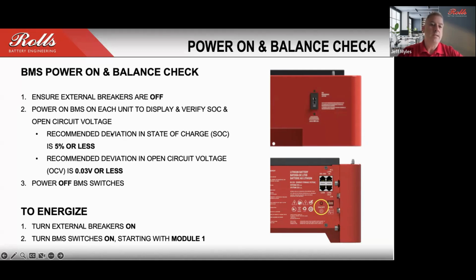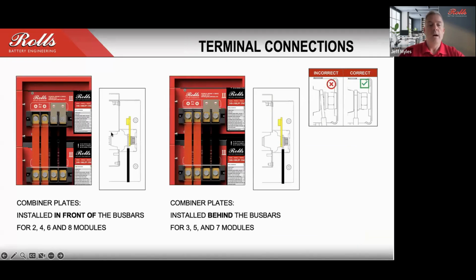When you do connect these units, if you are taking them on site and you haven't completed that process, you do have the flexibility once it's assembled to turn off the breakers to those units that don't need to be charged, and you can actually apply a charge independently to these units to balance them as well.